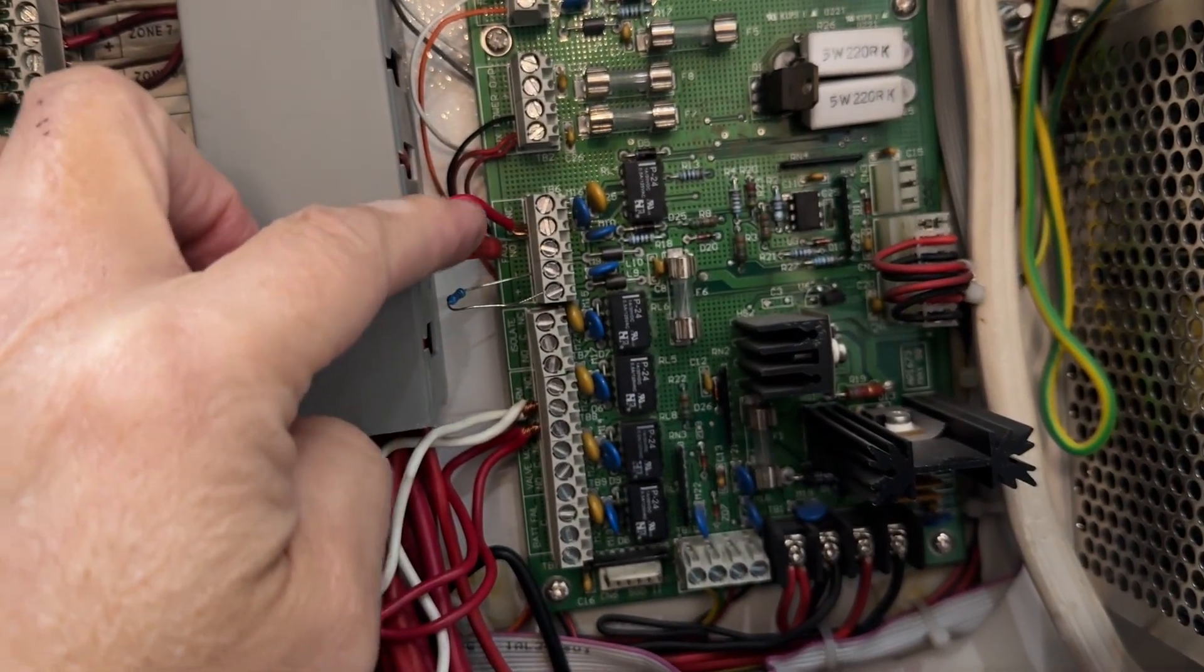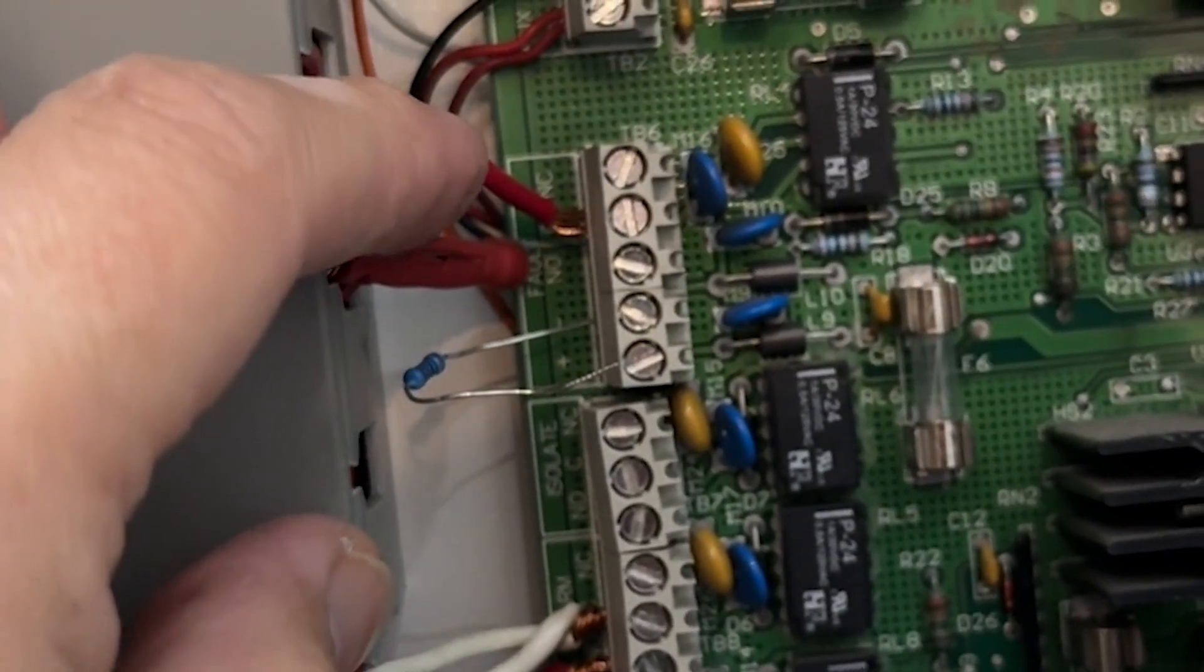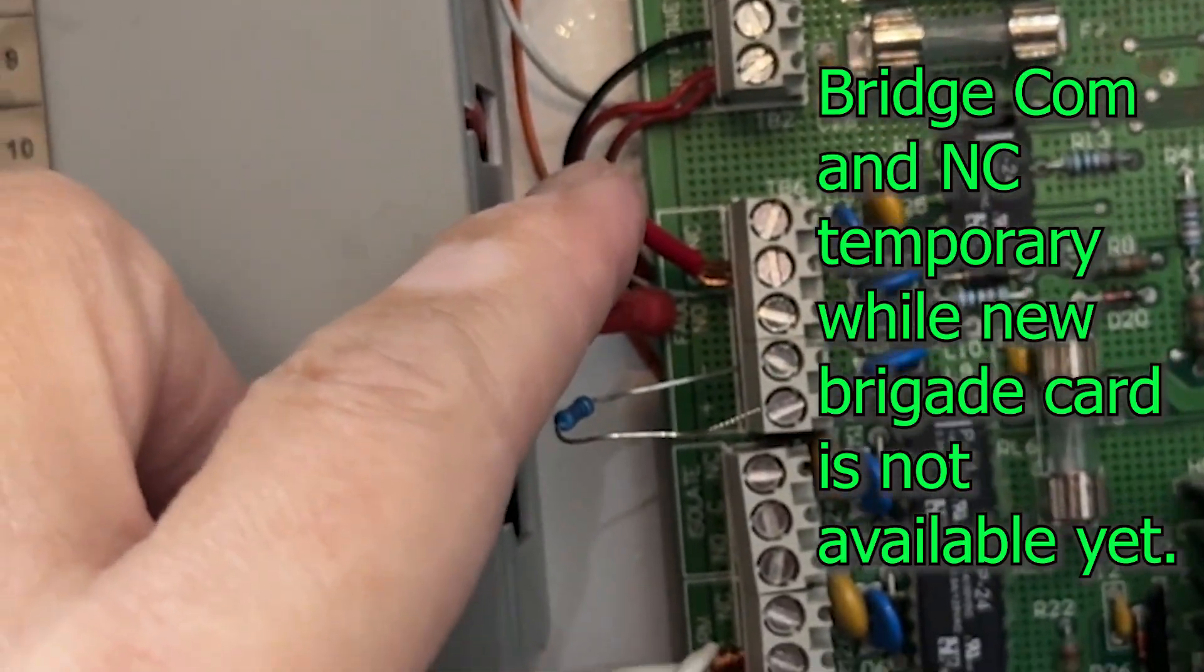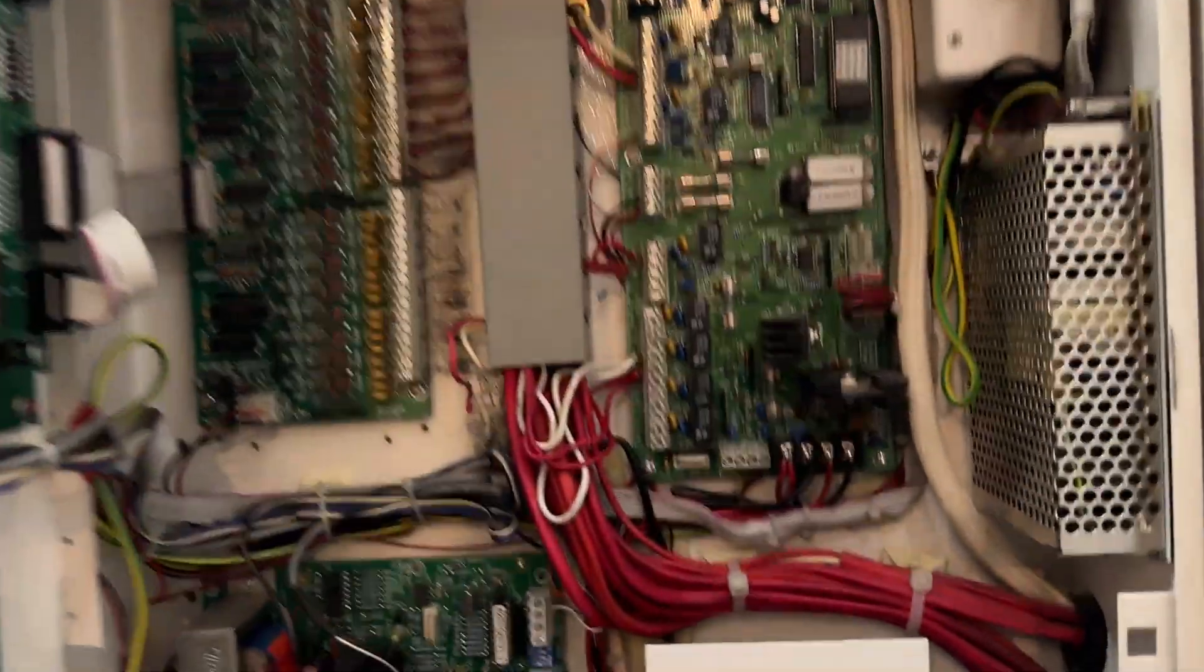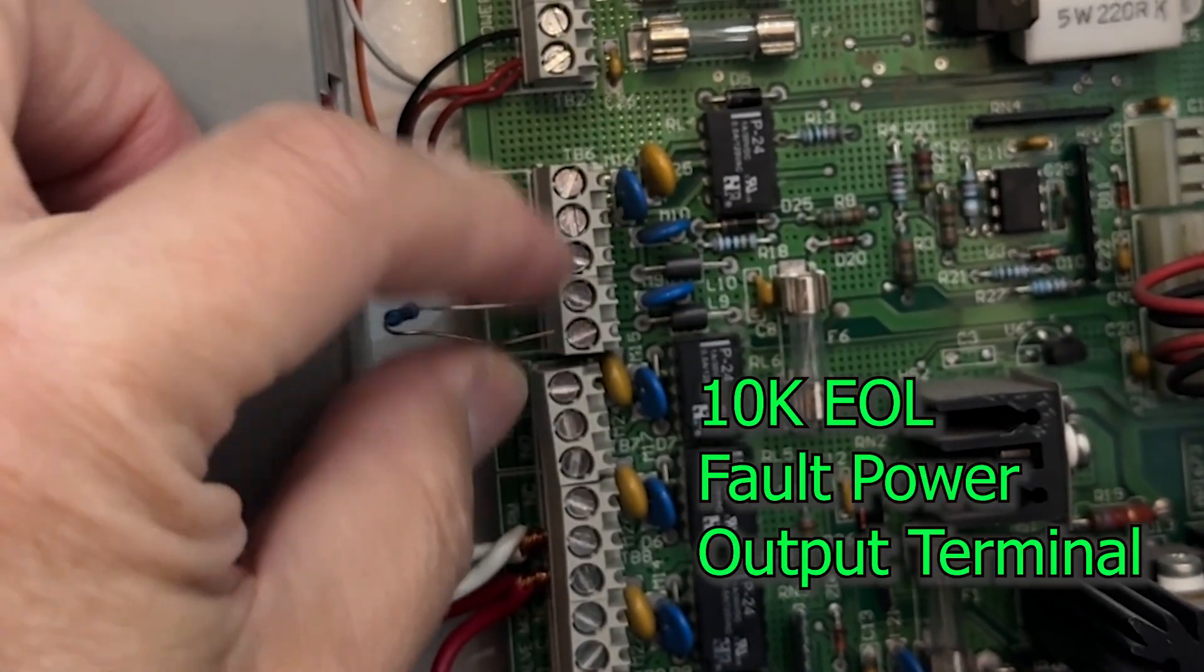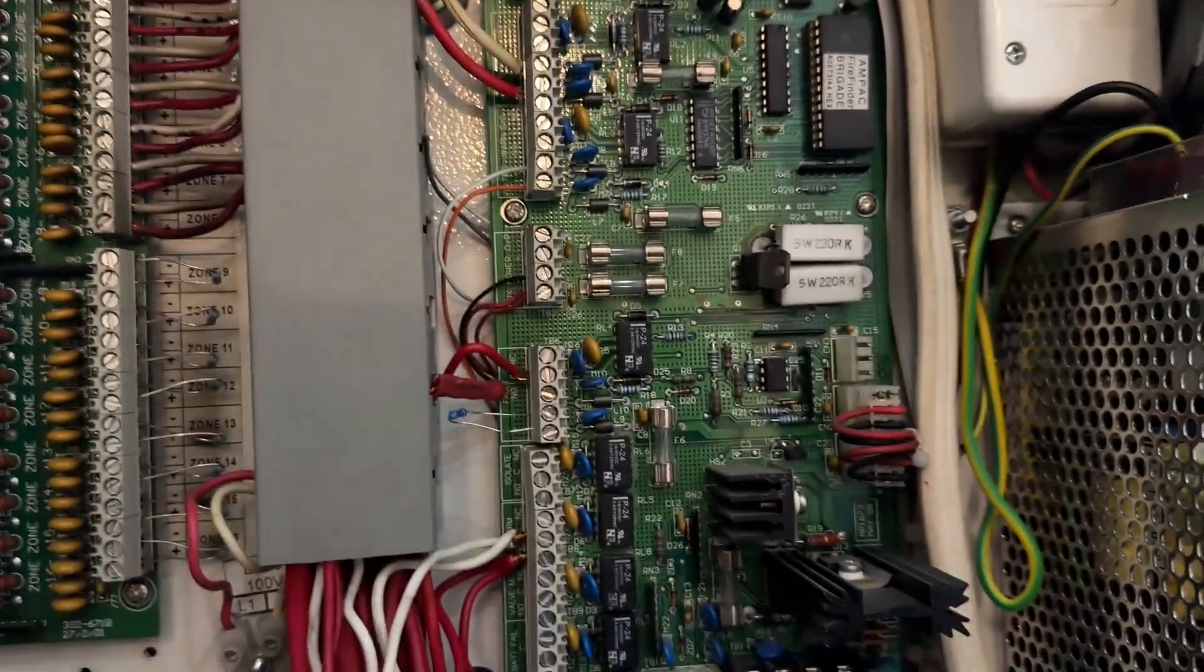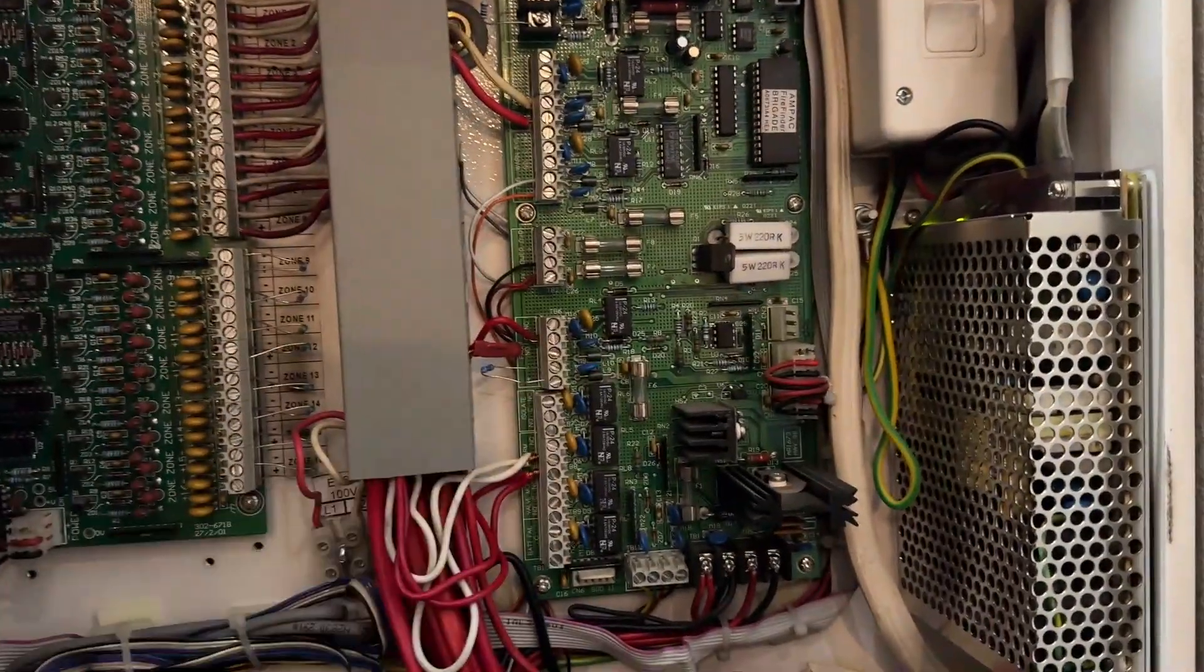Monitoring cable that goes to the main fire panel. So I won't have a fault in the main fire panel, which only stays here. And temporarily I removed this fault resistor, fault monitoring resistor, so that the fault will become permanent and not intermittent. I'll start replacing this brigade card.